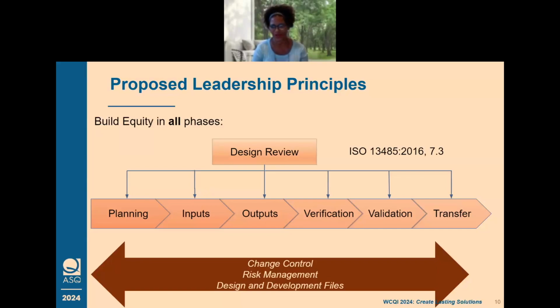We said earlier, 98% of devices on the market are cleared by the 510K. So nine times out of ten, the bulk of your validation will be through human factors studies, summative studies. At that point, you transfer to manufacturing, scale up, and you're ready to go. Throughout the entire process, you've got change control and risk management, and you're building your design and development file.